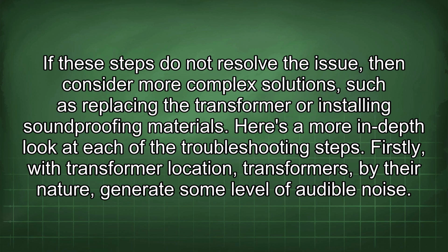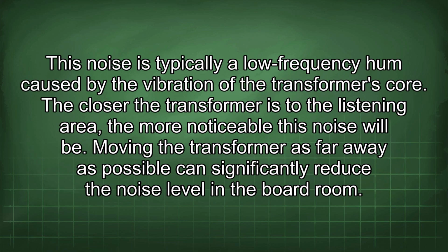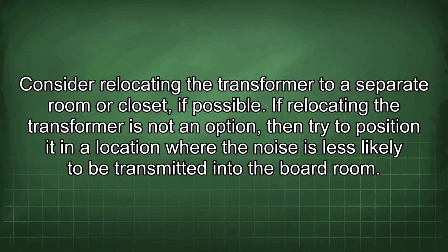Firstly, with transformer location, transformers, by their nature, generate some level of audible noise. This noise is typically a low-frequency hum caused by the vibration of the transformer core. The closer the transformer is to the listening area, the more noticeable this noise will be. Moving the transformer as far away as possible can significantly reduce the noise level in the boardroom. Consider relocating the transformer to a separate room or closet if possible.